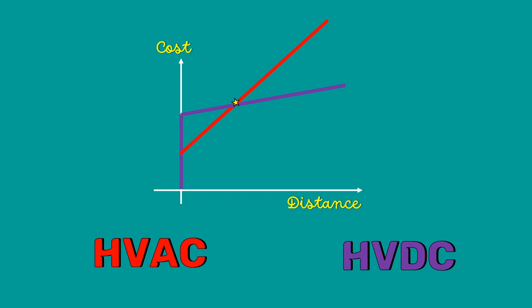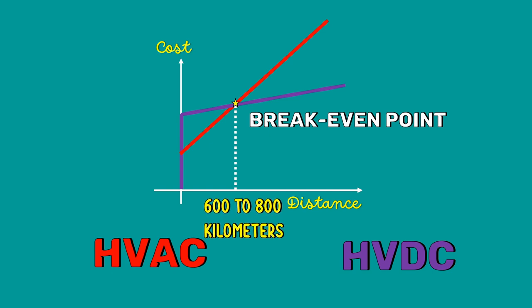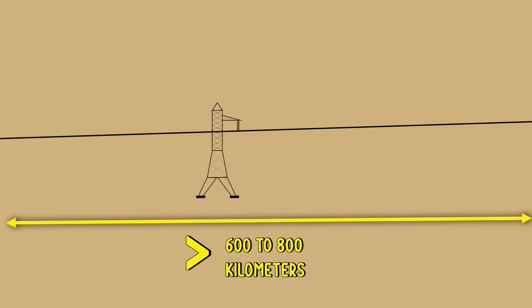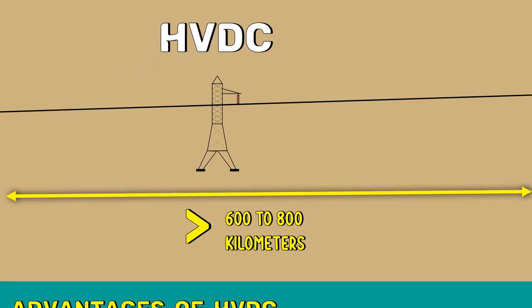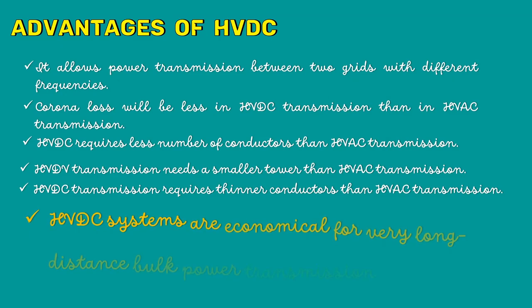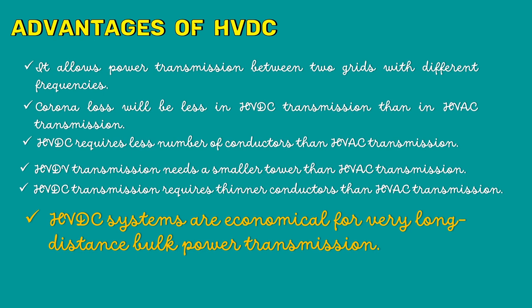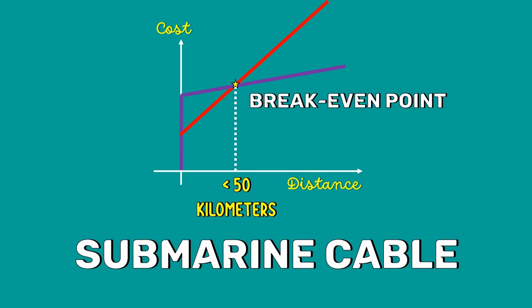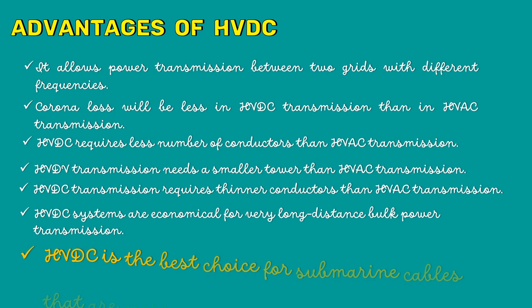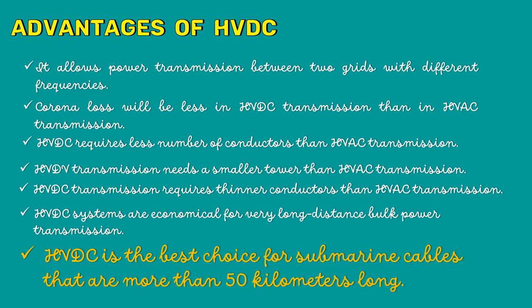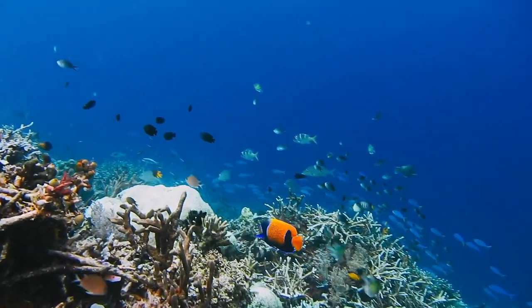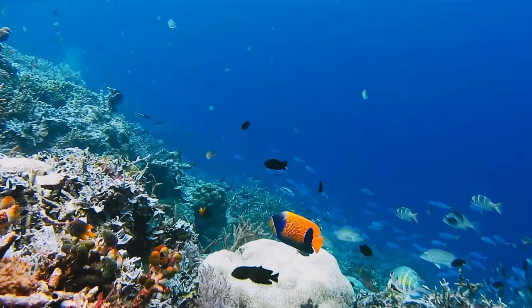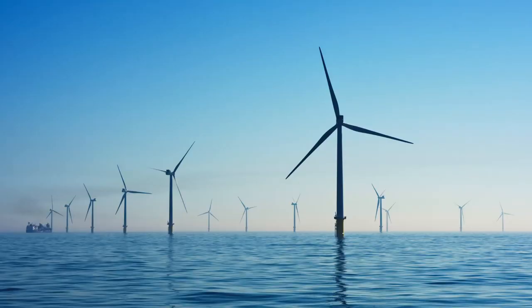The point of intersection on the graph is called the breakeven point. The breakeven distance for overhead transmission lines is estimated to be around 600 to 800 kilometers — so beyond this distance, HVDC is the best choice, as HVDC systems are economical for very long distance bulk power transmission. The breakeven distance for submarine cables is less than 50 kilometers, making HVDC the best choice for submarine cables over 50 kilometers long, such as transmitting electricity generated from the ocean to the shore.